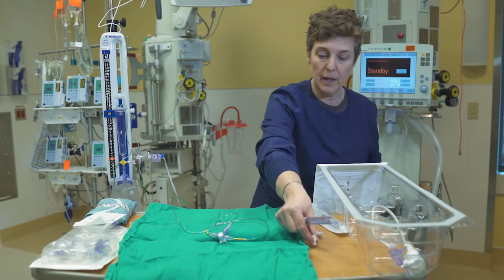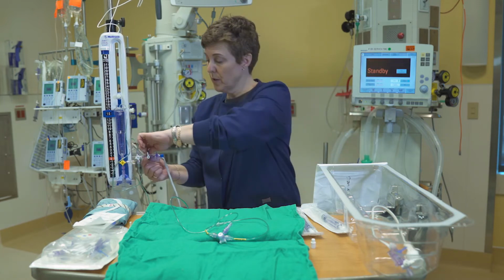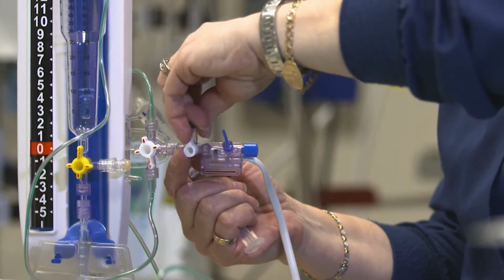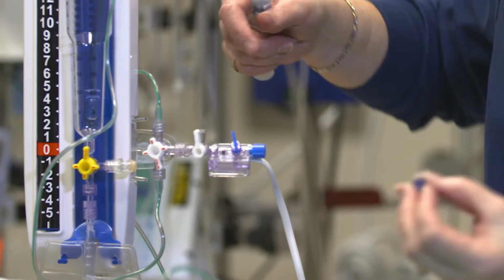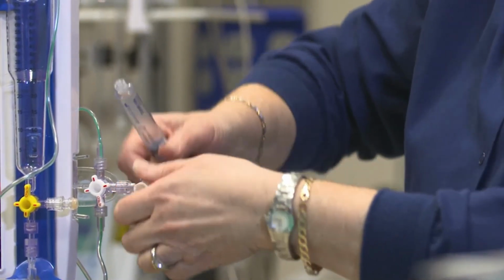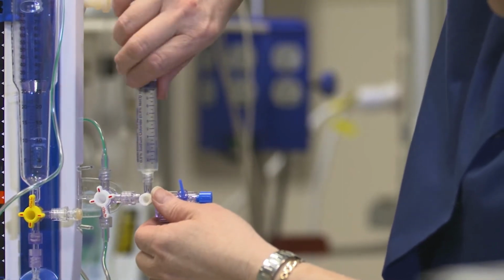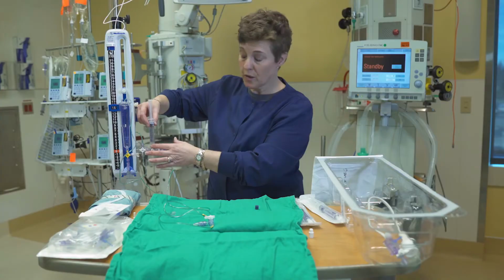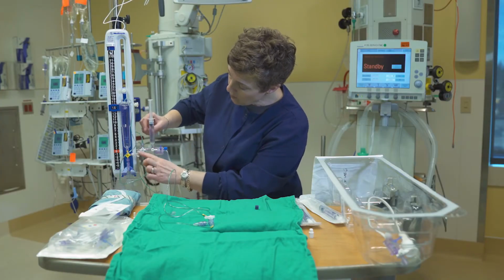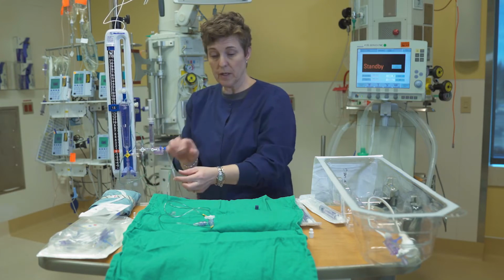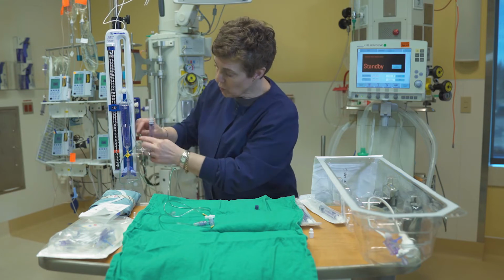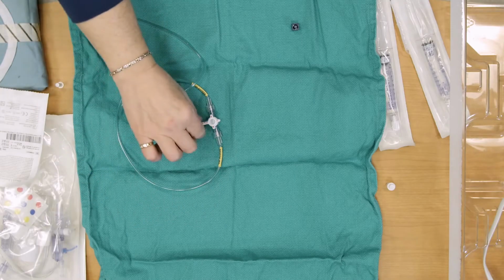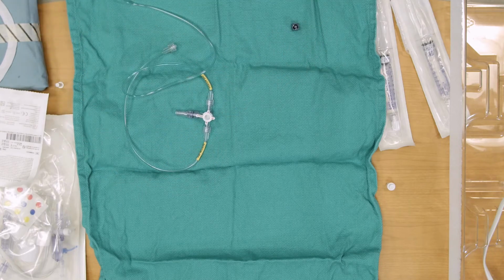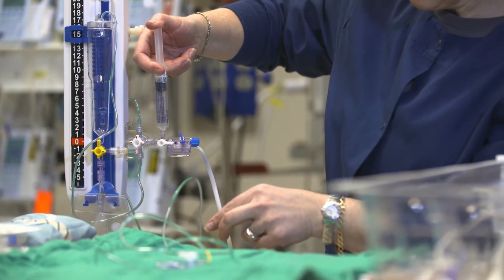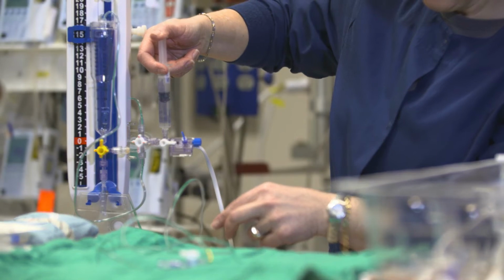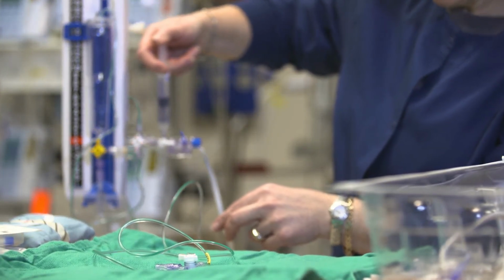There we go. So the cap that I had on before, actually I'm going to use this one. So from the far side of my transducer, okay, so now I'm going to flush the system. I've got my preloaded syringe mounted onto the stopcock that's behind the transducer. I have my stopcock closed to this side of the system because I'm going to flush this side right now. So I have it open to here, and I have it open through to the end. And that's why the stopcock is through like this. Okay, so now I'm just going to flush through. Clearing all the bubbles, as you would with anything else.